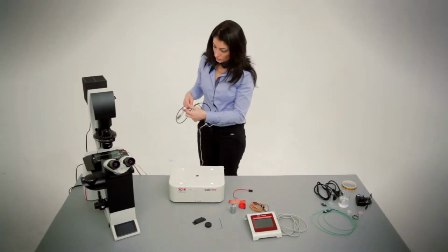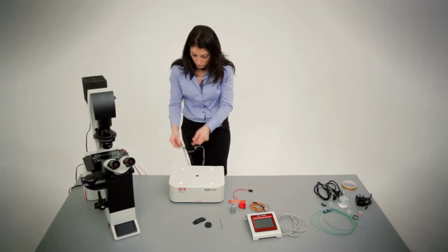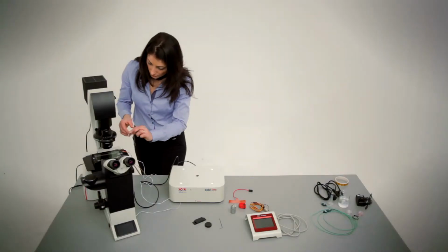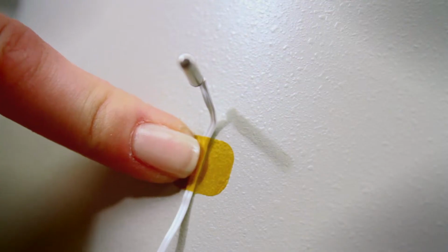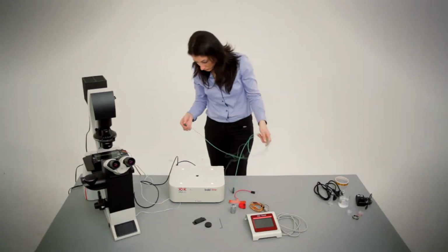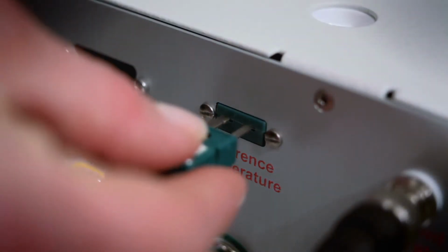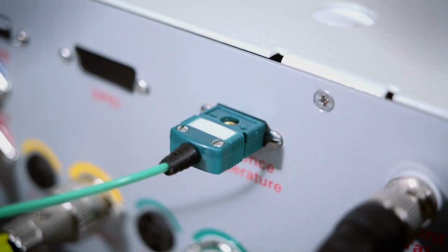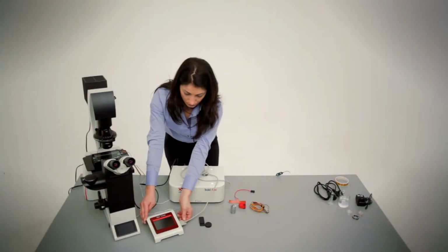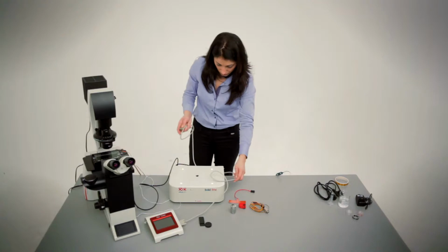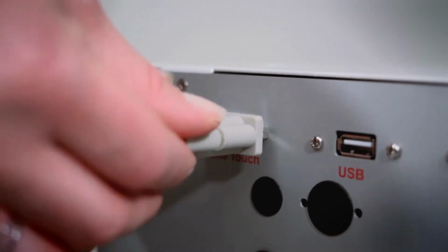Connect the room temperature sensor to the controller and attach it to the microscope pillar. Connect the green specimen feedback sensor. The two connectors are clearly marked on the rear panel. Connect the touchpad to the only RS-232 port of the controller.